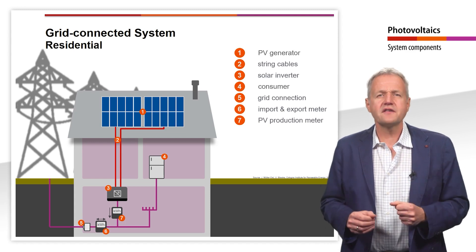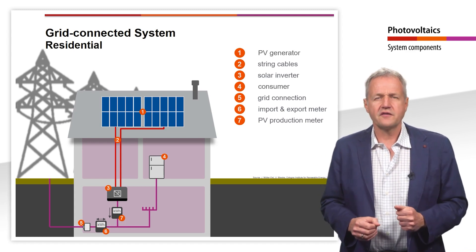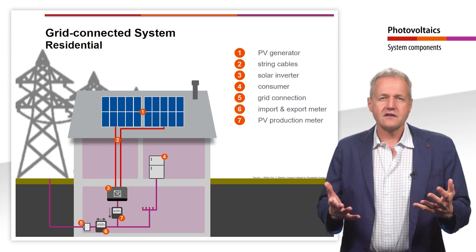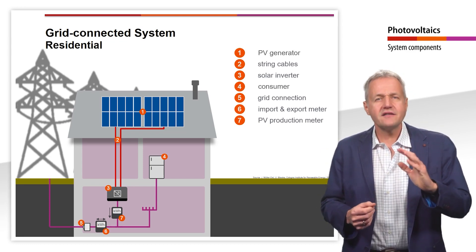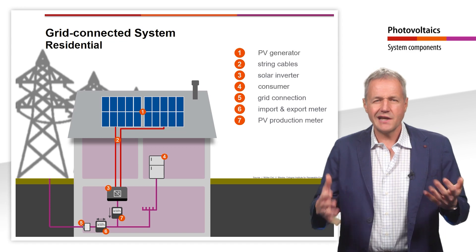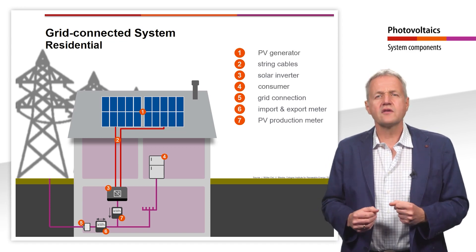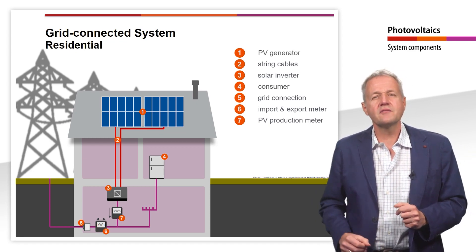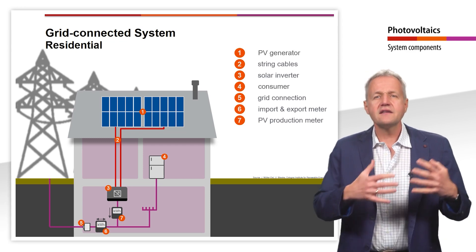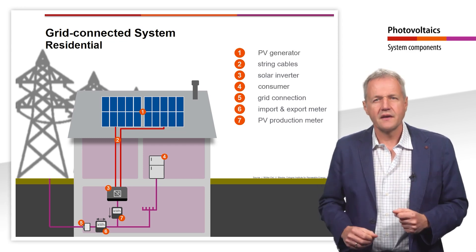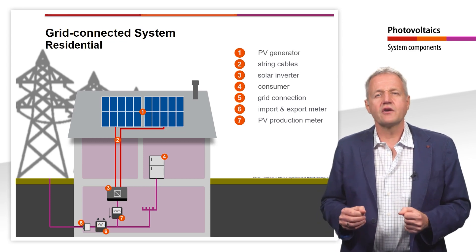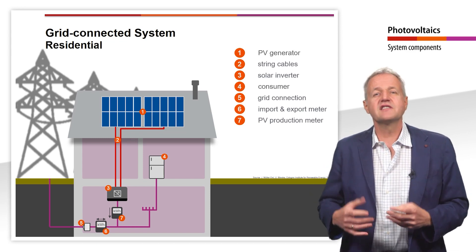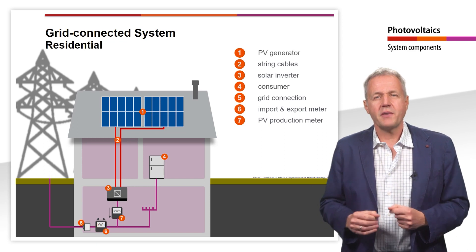This allows us to determine the self-consumption of the PV electricity. The self-consumption is calculated by dividing the self-consumed solar energy by the total electricity consumption in kWh. The self-consumed solar energy results from the difference between the total yield of the PV system, measured by meter 7, and the feed-in, measured by meter 6. The total electricity consumption is calculated from the self-consumed solar energy plus the electricity purchased, which is also measured by meter 6.